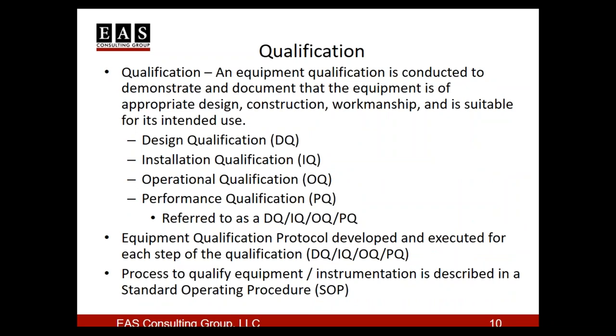The first thing to address the appropriate design, construction, workmanship, and suitability for use is what is referred to as a qualification. We talked about this if you joined us on our first webinar series - the DQ, IQ, OQ, PQ. So we're going to talk a little more about what that means: design qualification, installation qualification, operational qualification, and performance qualification. This is what is usually used in the laboratory to meet those requirements in 111, 211, or 117.